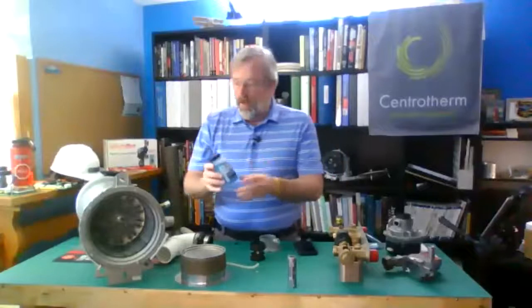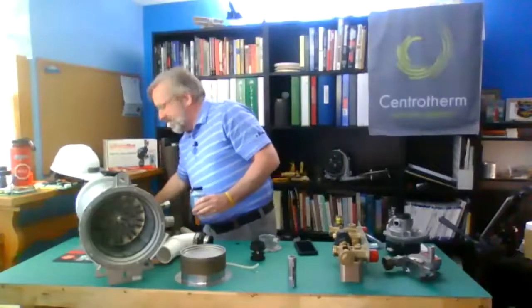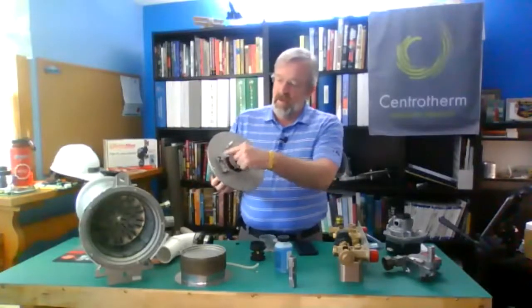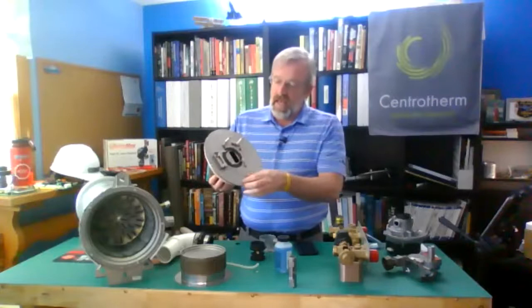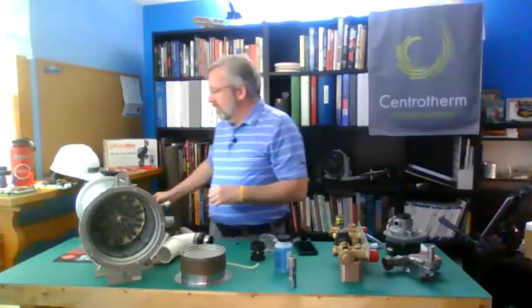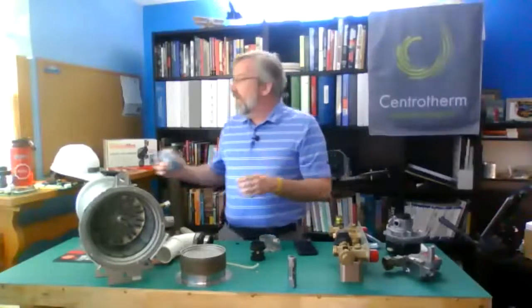leak detector. And what we're going to want to do is leak detect around where our fan's going to connect. We're going to test around our sight glass, and we're going to test around our screws. Why run it? Why not just fire the unit? Well, if we fire the unit, what happens? It gets hot, and our bubbles are going to dry. So if we do it this way, my bubbles don't dry. Also, if I find I've got a leak, I can continue to work with it without it getting too hot to touch, or without worrying about my bubbles drying up.